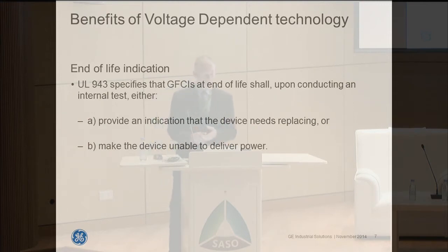A couple of the other things that are going on with voltage-dependent devices, the NEMA style, is that we've recently made some changes to the UL standards that help the device sense for itself when it's reached its end of life. We were seeing some issues a while ago where voltage surges were causing some lack of reliability in the products, and those issues really have been addressed through significantly better robustness to voltage surges based on the UL standards changes that are really defining higher thresholds for these devices. And in addition, they're also identifying and self-testing, and they give the user an indication and will actually take themselves out of service if they're not functioning correctly. So they really tend to be very safe devices and will take themselves out of service if they're not functioning correctly.